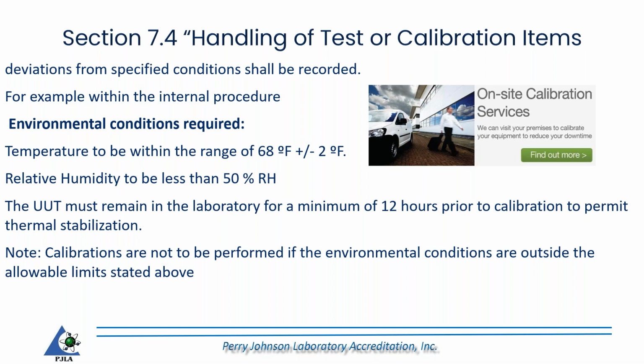Within the procedure, it says calibrations are not to be performed if the environmental conditions are outside these allowable limits. So a deviation would be, hey, if you were to do a test or calibration, there were your parameters set forth, and you happen to go in there and it was 65 degrees Fahrenheit, for example, then a consultation needs to be held with the customer as far as proceeding with the test or calibration.